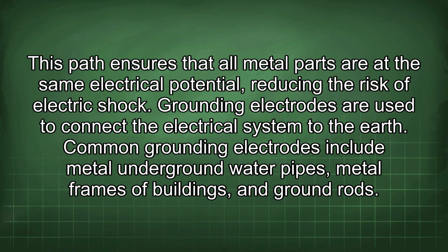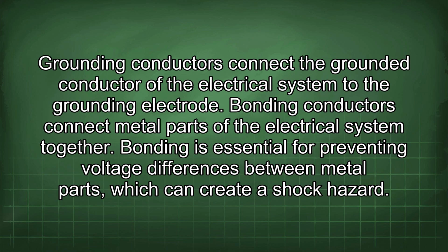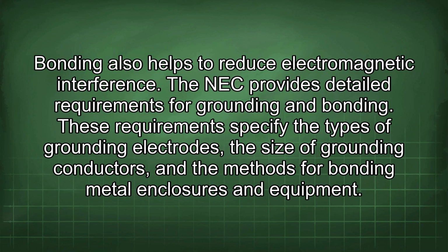Grounding electrodes are used to connect the electrical system to the earth. Common grounding electrodes include metal underground water pipes, metal frames of buildings, and ground rods. Grounding conductors connect the grounded conductor of the electrical system to the grounding electrode. Bonding conductors connect metal parts of the electrical system together. Bonding is essential for preventing voltage differences between metal parts, which can create a shock hazard. Bonding also helps to reduce electromagnetic interference.